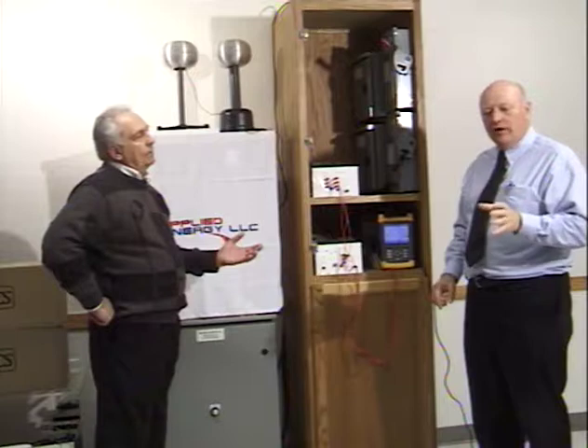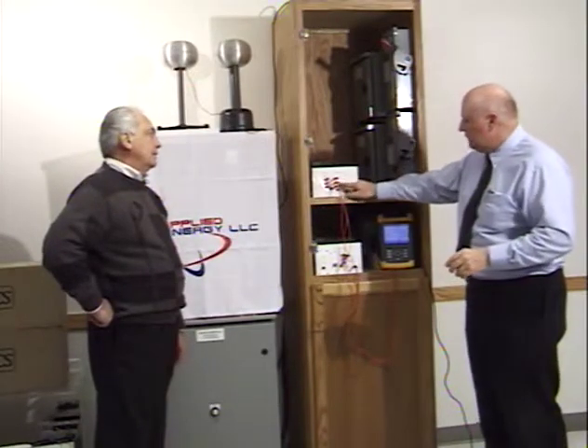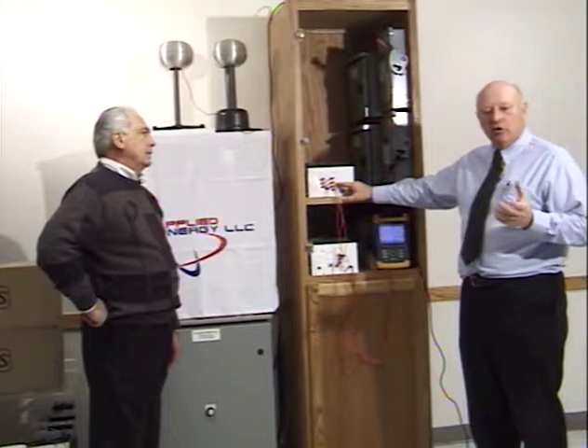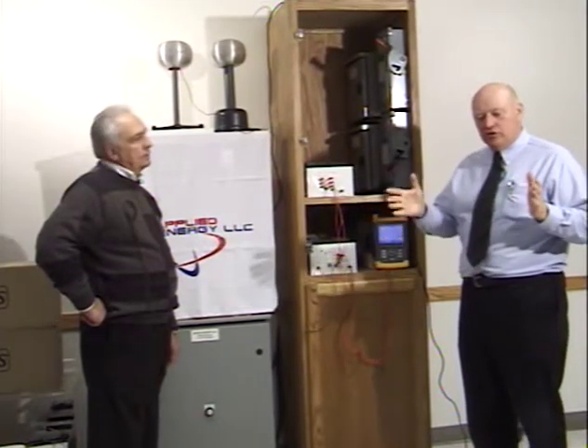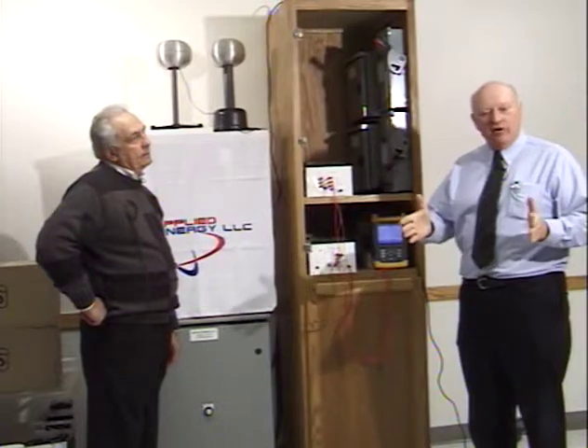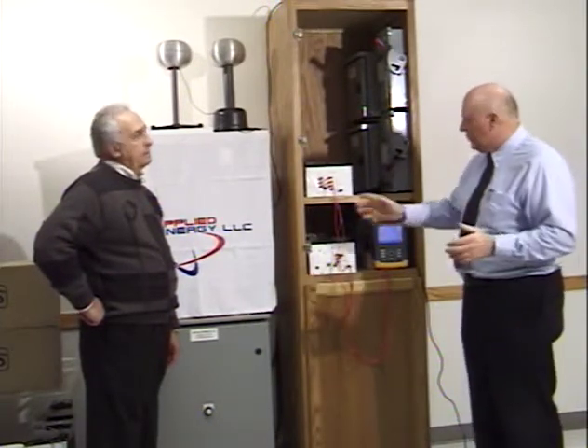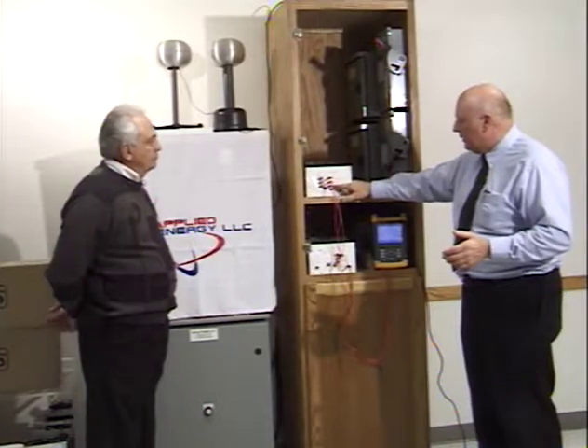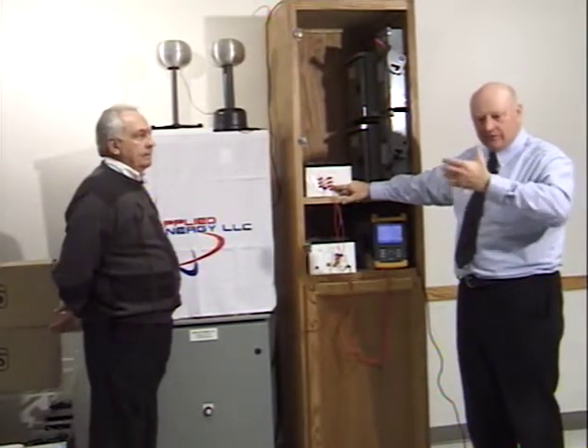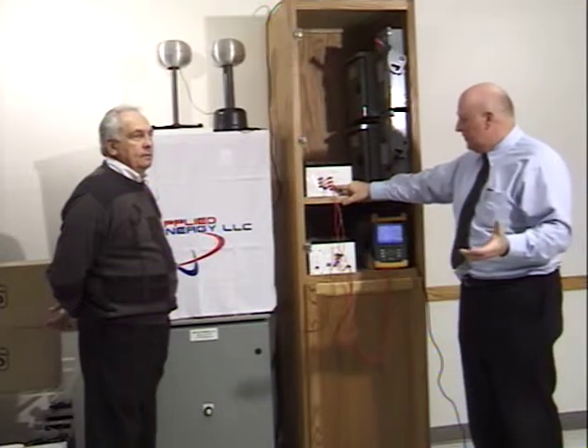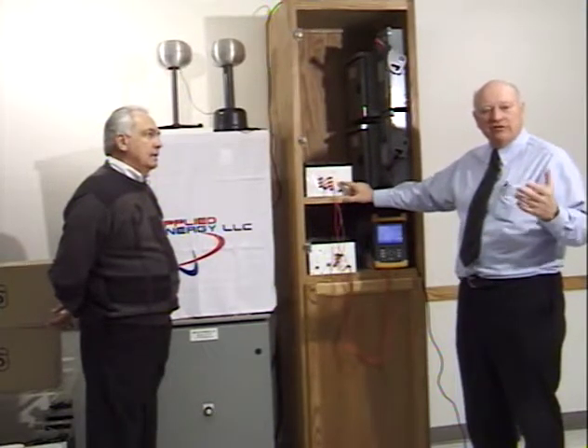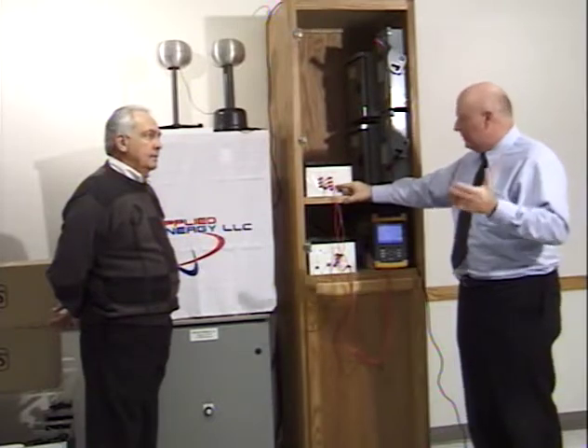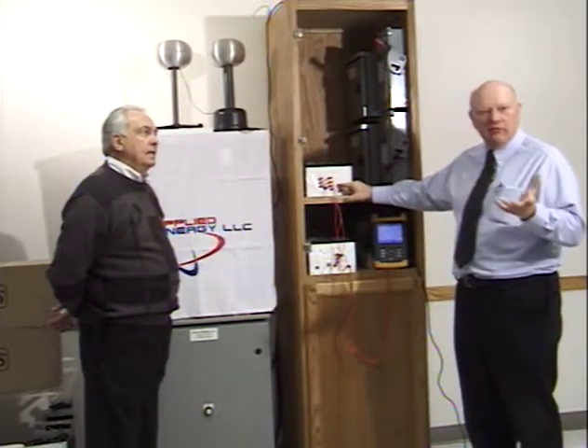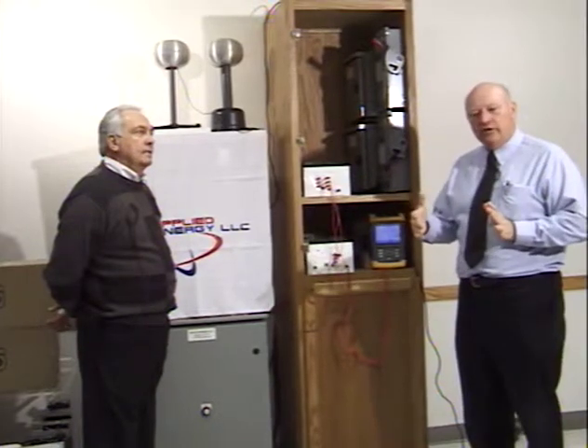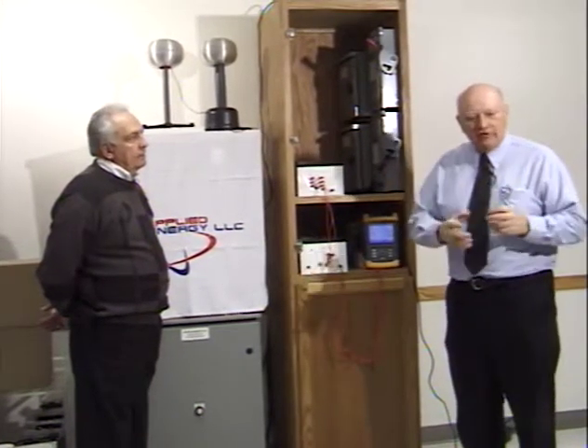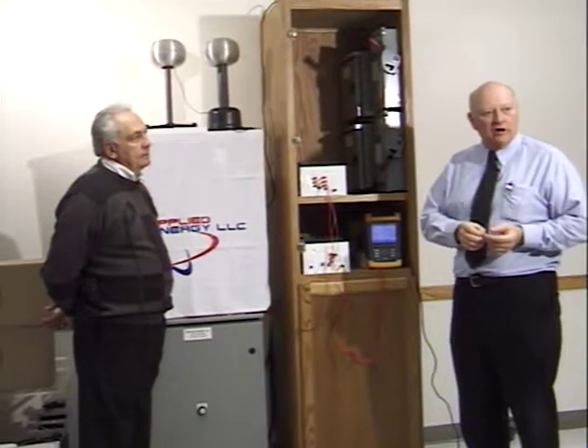Now, one benefit of that is because of all the noise between a drive and a motor, most manufacturers tell us that you shouldn't exceed 100 cable foot or have more than 100 foot of wire between a drive and a motor. Now, we have already reduced the noise by not 5%, but 85%. We've already tested well over 1,000 feet of motor power cable between the drive and motor very reliably. So the 100-foot distance because of reflected wave, let's just call it noise, is no longer a problem.